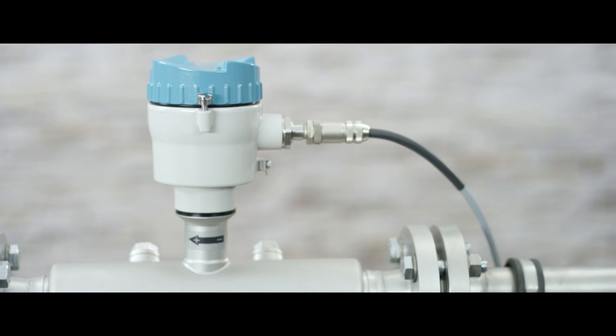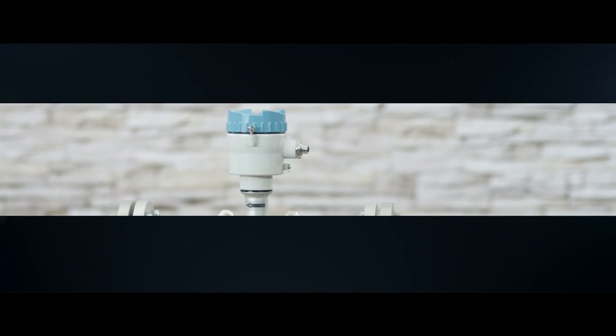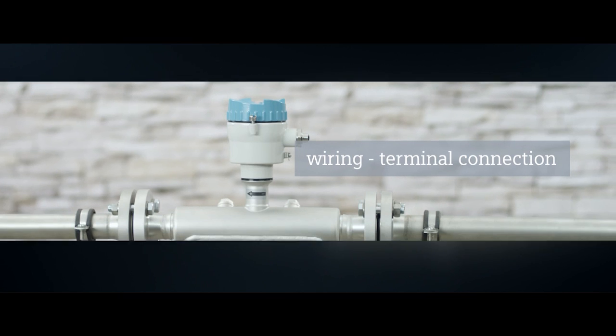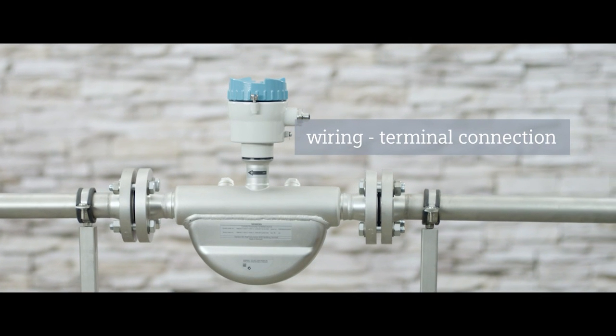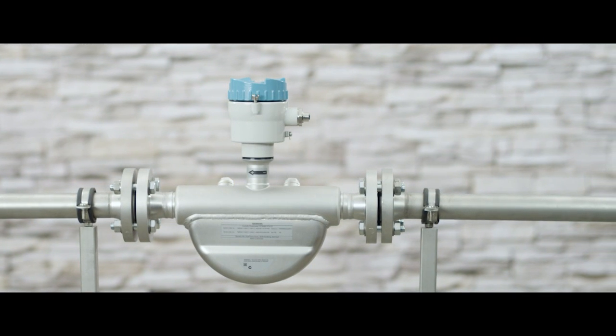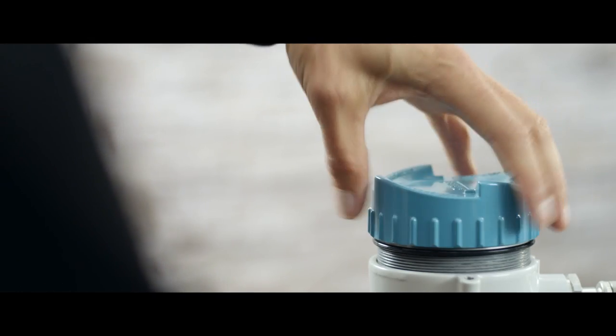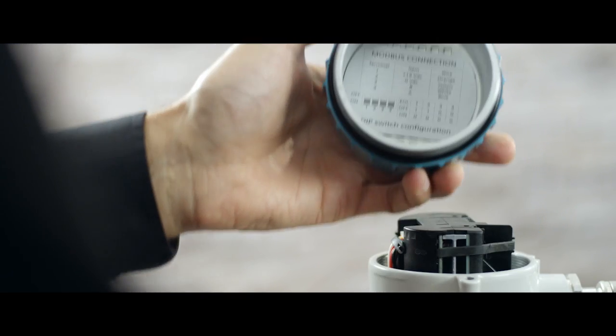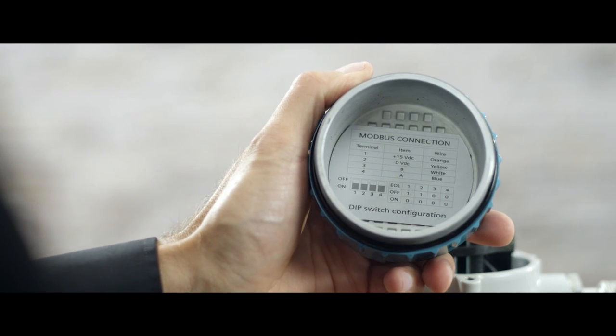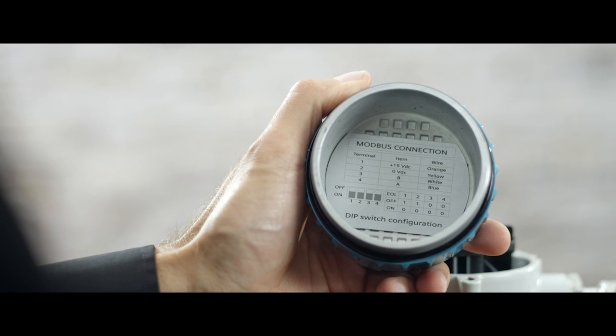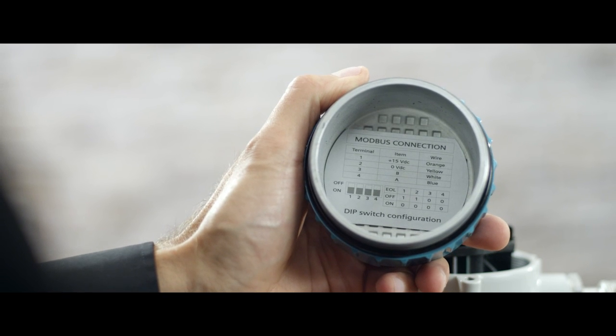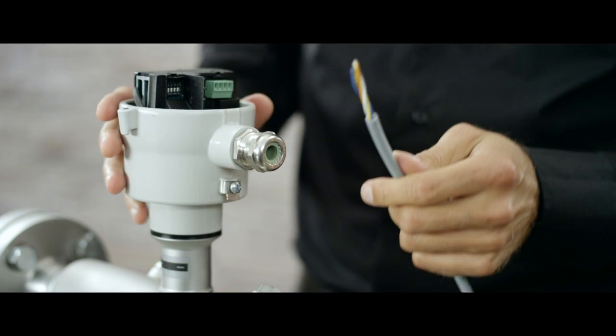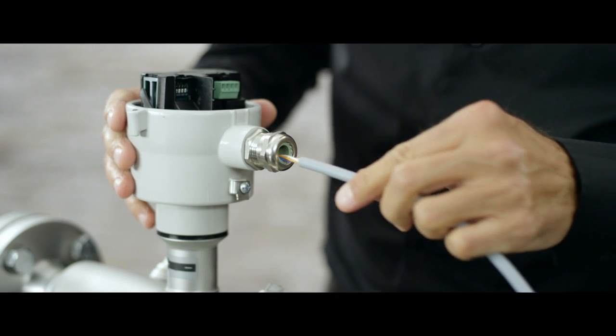The Siemens FC410 is also available with a cable duct, in which case you must connect the cables directly in the measurement instrument. To do so, undo the lock screw and remove the cover. A circuit diagram for the wiring can be found on the back of the cover. Thread the cable through the cable duct and now connect the cables.